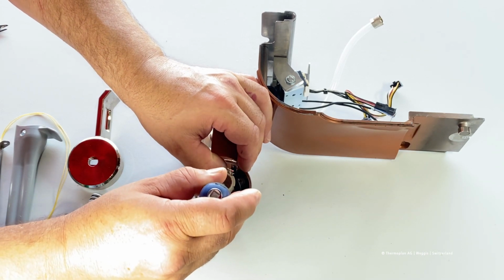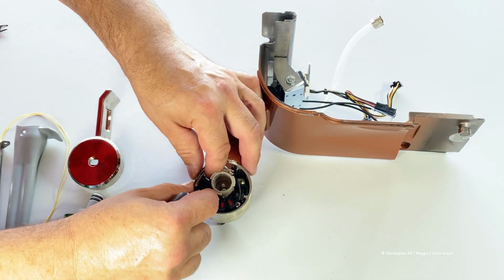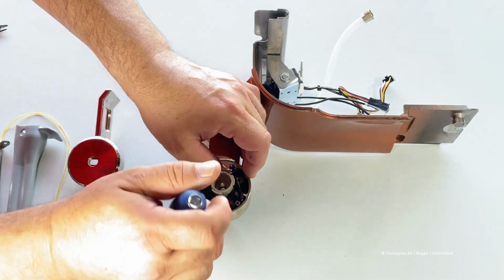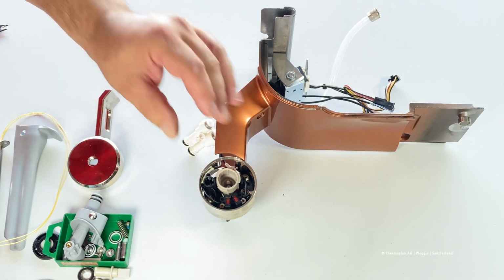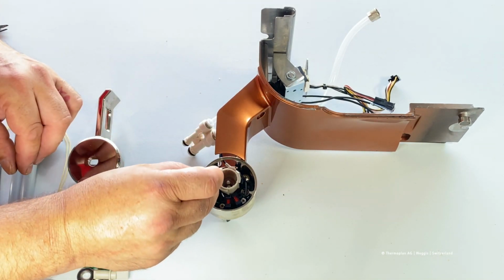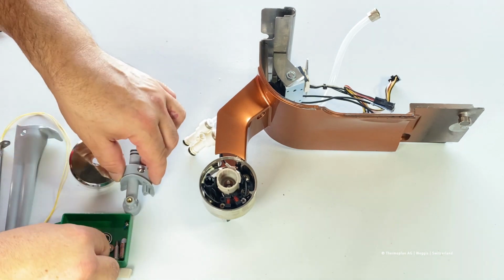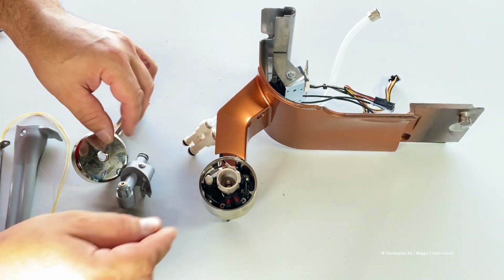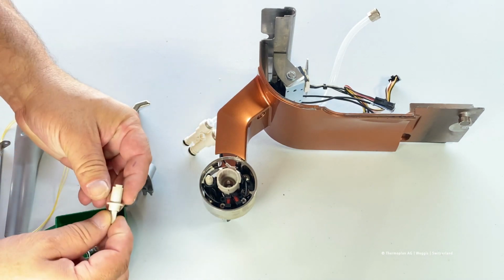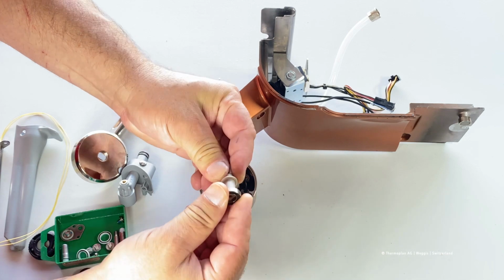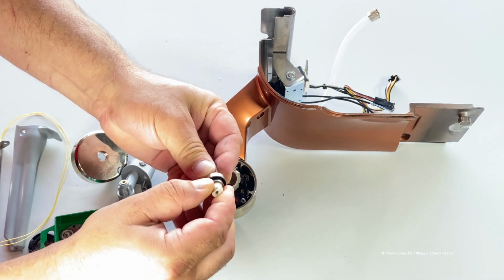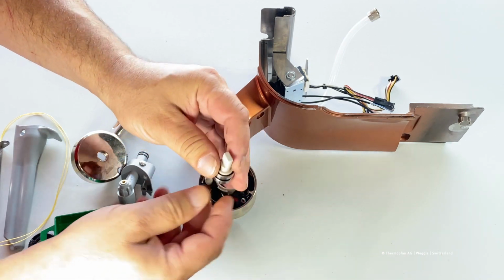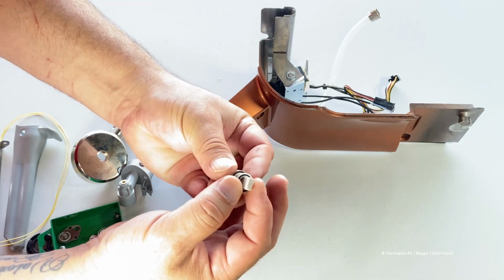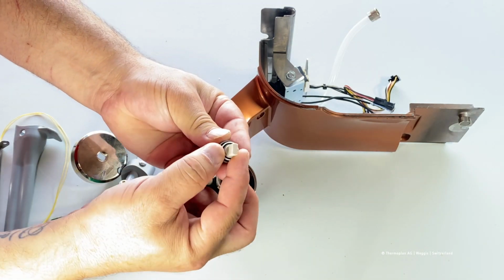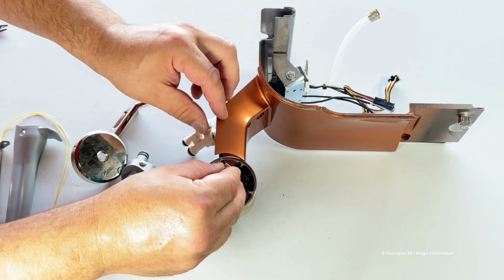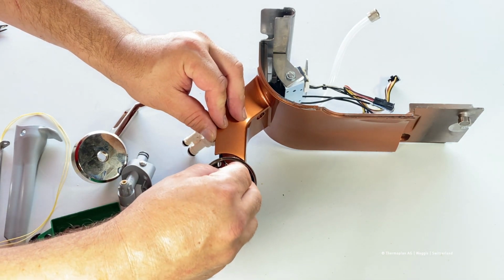So we start now to put everything back together with attaching the two photoelectric sensors. Make sure the routing is proper. Then I insert the spring, the plunger, then the bearing to the shaft, the spacer, the other bearing, and then the seal. Make sure the seal is in the right position, as I showed, facing the steam direction. Then I can push the shaft inside.